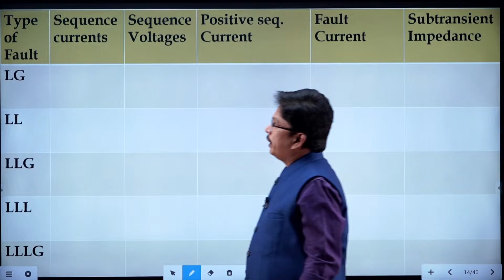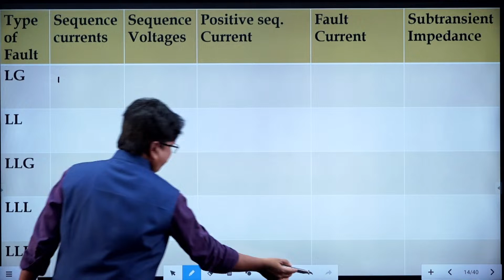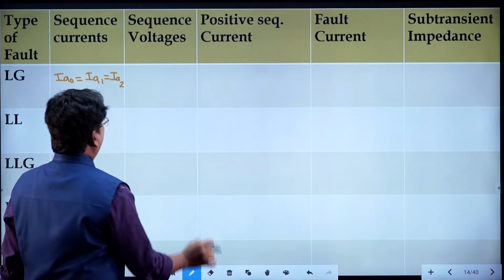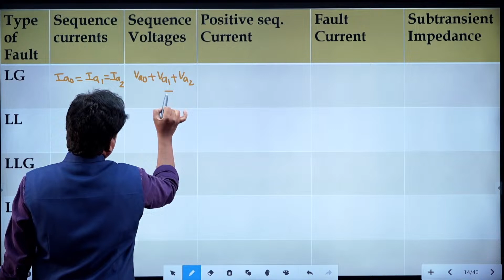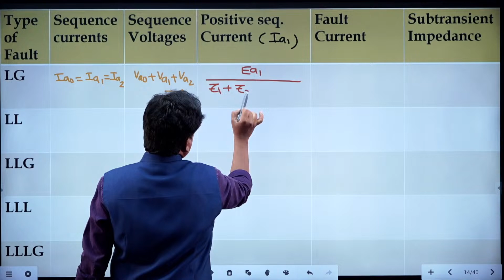So in case of LG fault, the sequence currents, we can say all are same. IA0 is equivalent to IA1 is equivalent to IA2, all are same in case of the LG fault. Sequence voltage sum will be 0: VA0 plus VA1 plus VA2 is equivalent to 0. The positive sequence current IA1 is equivalent to EA1 divided by Z1 plus Z2 plus Z0 plus 3Zn, and if the fault impedance is there, you can add that fault impedance also, plus 3 times ZF, right? That is the fault impedance. If there is no fault impedance, substitute this as 0. If there is no neutral impedance, substitute this as 0.